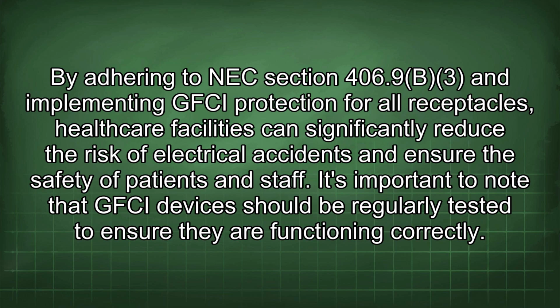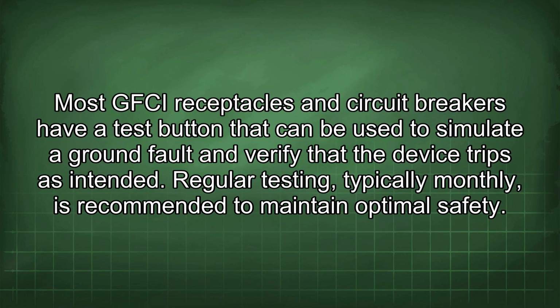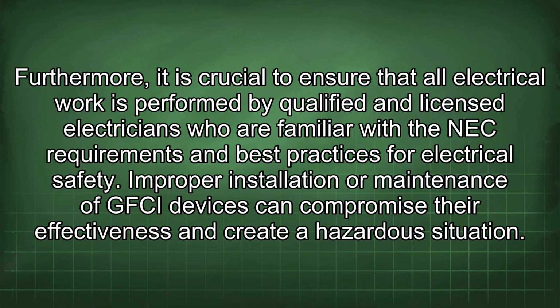It's important to note that GFCI devices should be regularly tested to ensure they are functioning correctly. Most GFCI receptacles and circuit breakers have a test button that can be used to simulate a ground fault and verify that the device trips as intended. Regular testing, typically monthly, is recommended to maintain optimal safety. Furthermore, it is crucial to ensure that all electrical work is performed by qualified and licensed electricians who are familiar with the NEC requirements and best practices for electrical safety. Improper installation or maintenance of GFCI devices can compromise their effectiveness and create a hazardous situation.